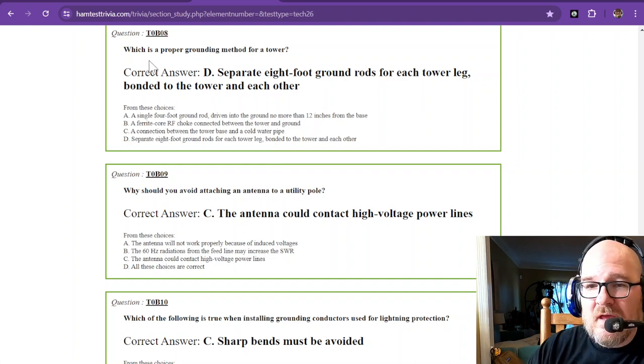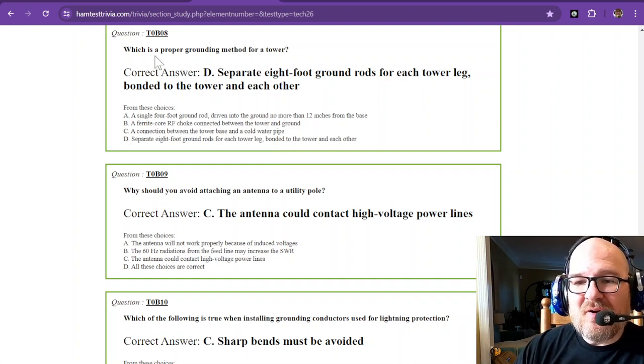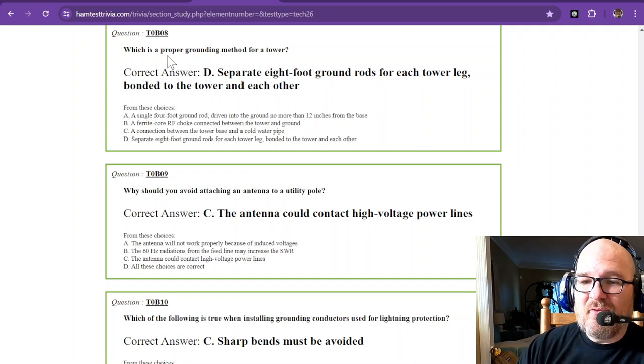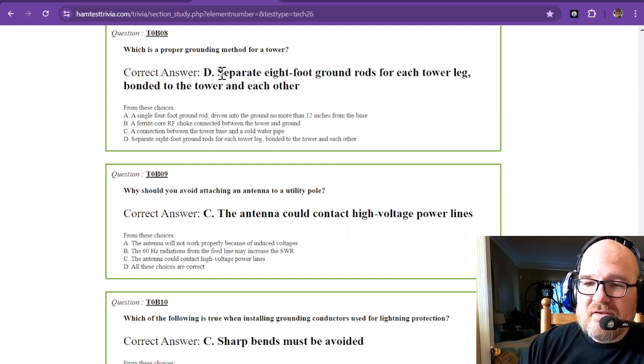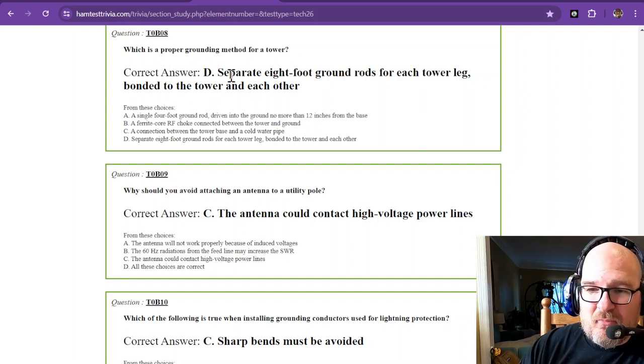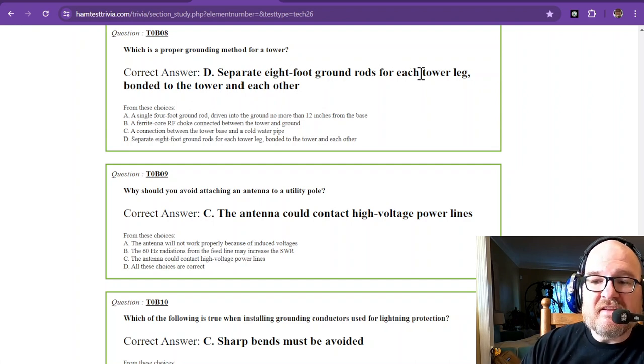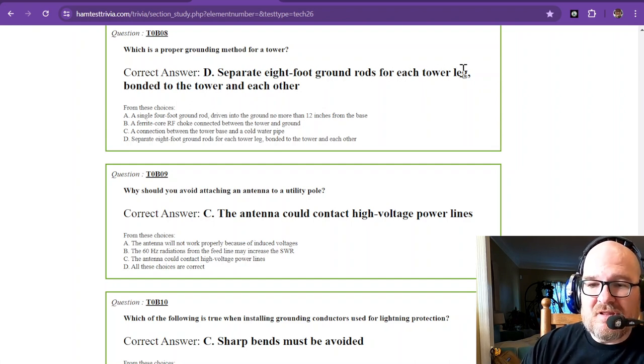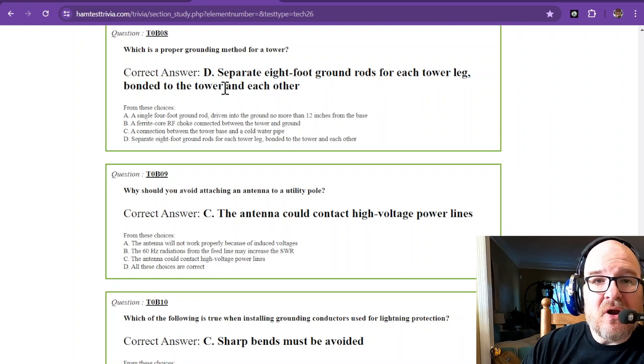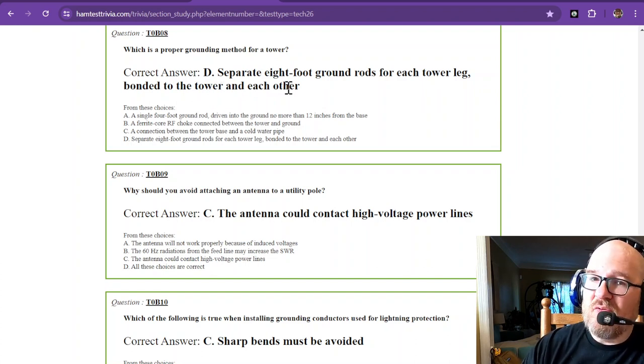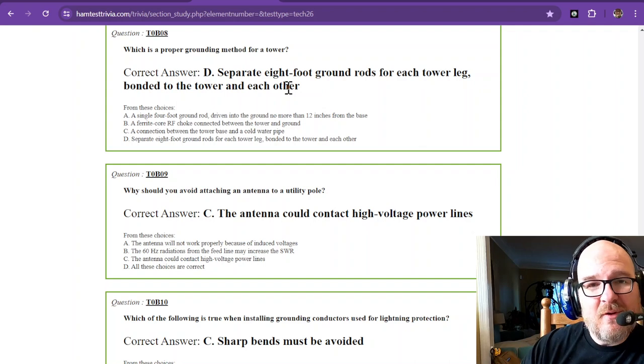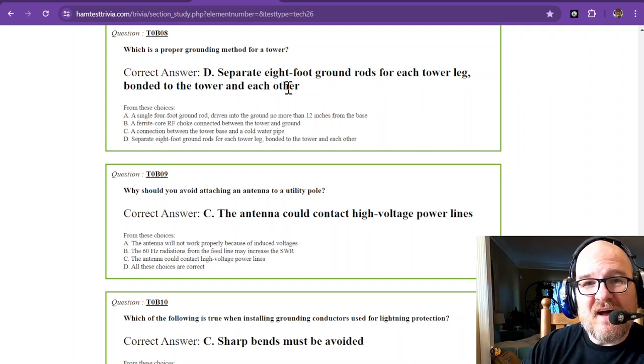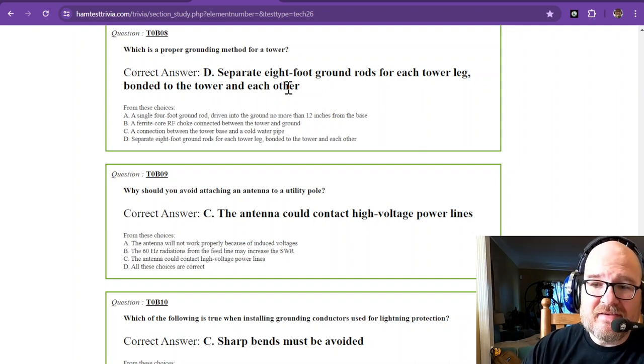Which is a proper grounding method for a tower? The correct answer is separate eight-foot ground rods for each tower leg, bonded to the tower and each other. That is the only correct answer. So if you have Rohn 25 tower, it has three legs, you're going to have three ground rods and three bondings to those legs, one to each leg.